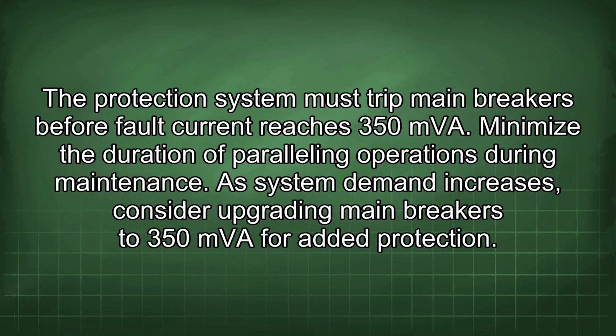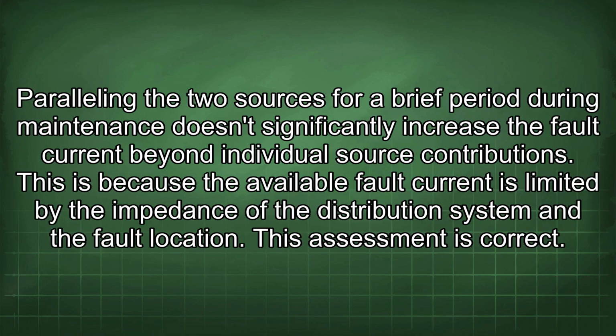The protection system must trip main breakers before fault current reaches 350 MVA. Minimize the duration of paralleling operations during maintenance. As system demand increases, consider upgrading main breakers to 350 MVA for added protection. Paralleling the two sources for a brief period during maintenance doesn't significantly increase the fault current beyond individual source contributions. This is because the available fault current is limited by the impedance of the distribution system and the fault location.